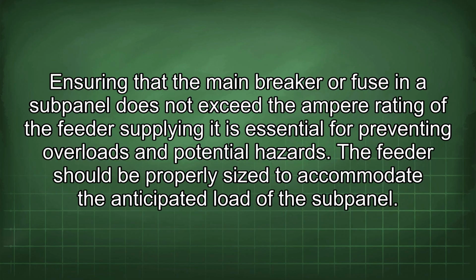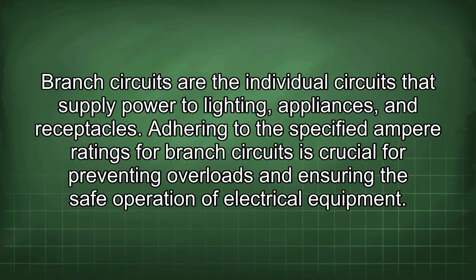Ensuring that the main breaker or fuse in a subpanel does not exceed the ampere rating of the feeder supplying it is essential for preventing overloads and potential hazards. The feeder should be properly sized to accommodate the anticipated load of the subpanel. Branch circuits are the individual circuits that supply power to lighting, appliances, and receptacles.